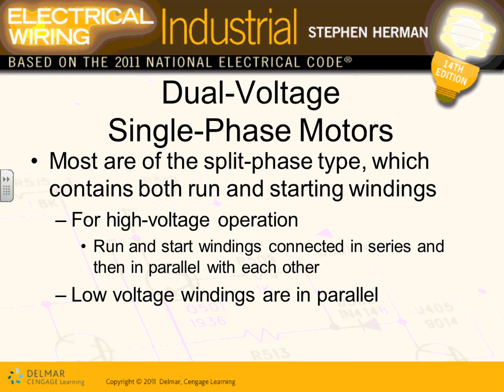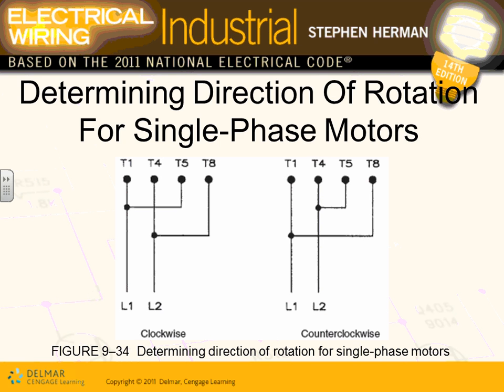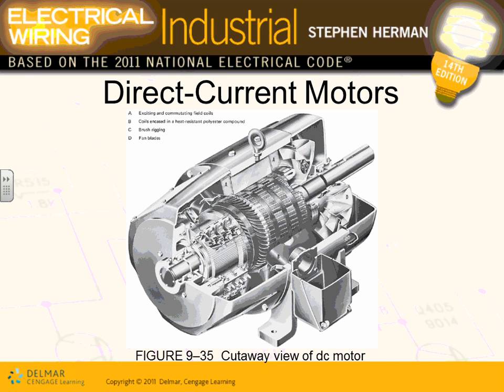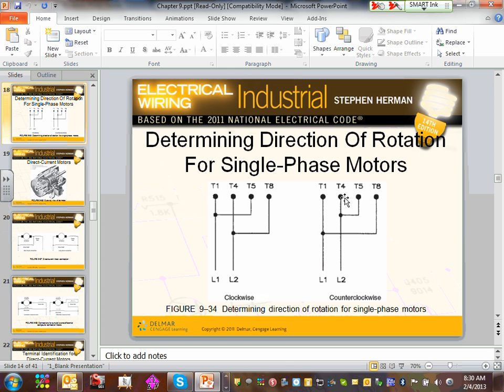Okay, dual voltage single phase motors. If you have a single phase motor, guys, almost all motors are dual voltage because it gives you two voltages to run your equipment on, voltage 1, voltage 2. We have split phase, which could have both running and starting windings. You can run them at high voltage or low voltage. Low voltage are in parallel. I don't know if I have an induction picture of that one, very easy.